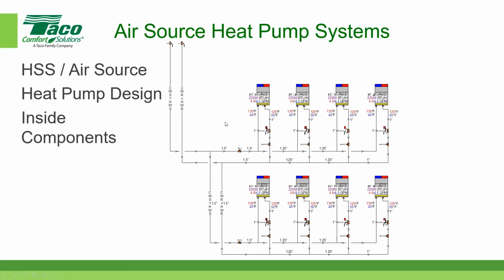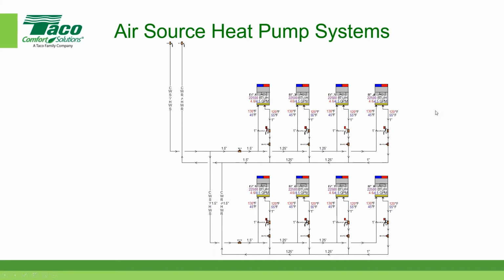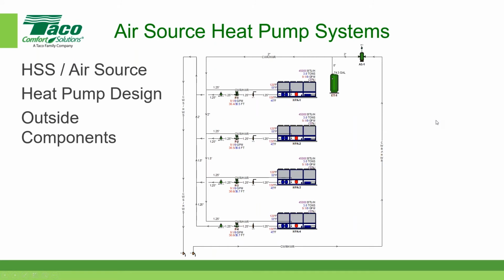So I'm supplying 45 degree Fahrenheit chilled water in the summertime from my air to water heat pump, and in the wintertime 130 degrees. Now again, just like I said earlier, the heat pump that's producing the hot water is sending the hot water to the terminal unit, in this case fan coils. So the fan coil has to be selected for an entering water temperature of about 130 degrees Fahrenheit. That's my design condition. So that gives you a quick snapshot of what the actual system configuration is going to look like.